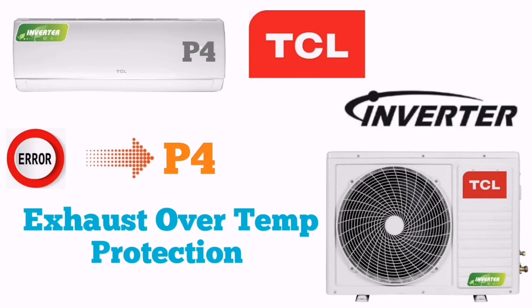And if you see it showing the 20 kilo ohms at 25 degrees Celsius, it means your exhaust temperature sensor is okay. Then you have to replace your control board and your unit will be in working condition.